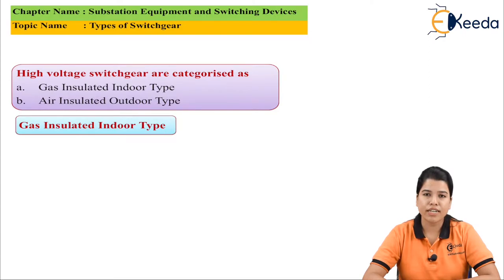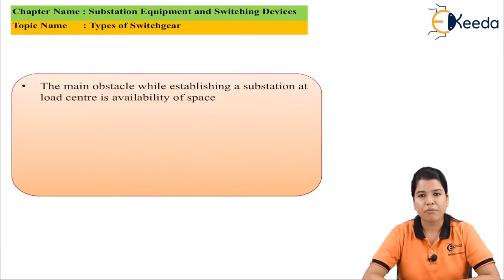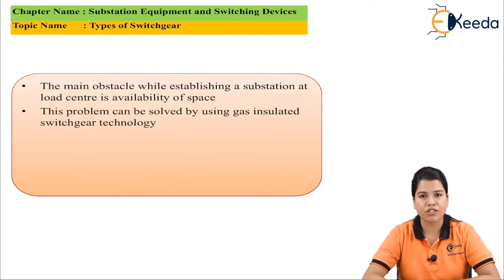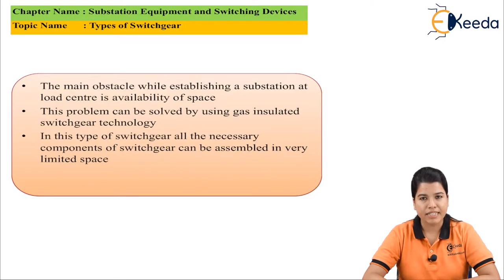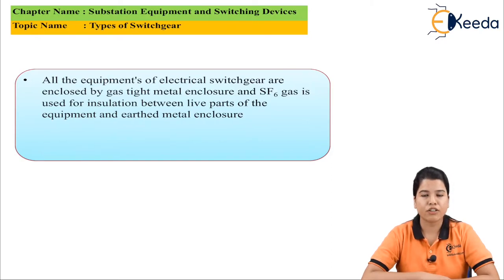The gas insulated indoor type switchgear is shown in the figure. The main obstacle while establishing a load center is the availability of space. This problem can be solved by using gas insulated indoor switchgear, since the space required for installation is very less and all components can be assembled in very little space. It is a kind of metal enclosed switchgear where all equipment is enclosed in a gas-tight metal box and sulfur hexafluoride gas is used for insulation.